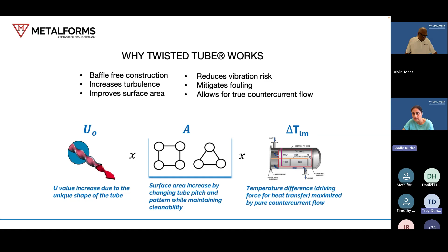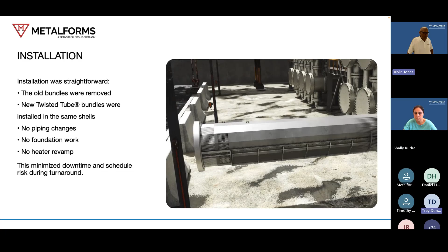Alvin, you can talk about the installation. Okay, yeah, the installation was very straightforward. All of these exchangers have removable bundles because they're in fouling service. The customer has to be able to pull those exchangers from time to time and clean them. What our offer was about was, instead of pulling those exchangers to clean them, you pull them and replace them with this more efficient twisted tube bundle, saving the customer in terms of piping modifications, in terms of foundation changes, and avoiding having to re-rate a fired heater.